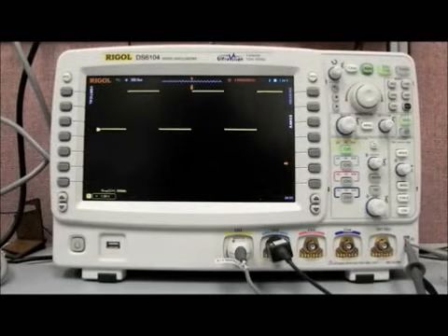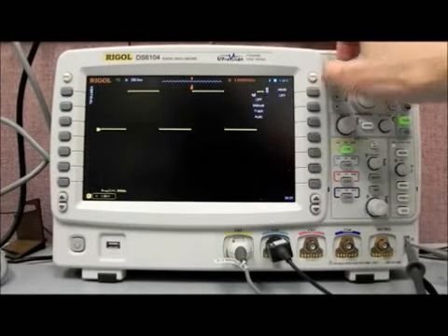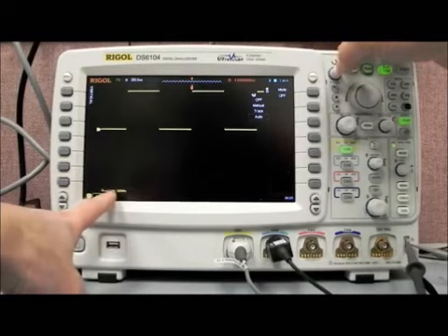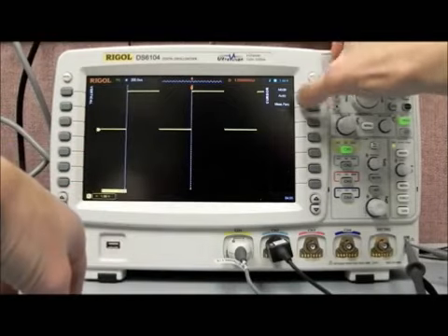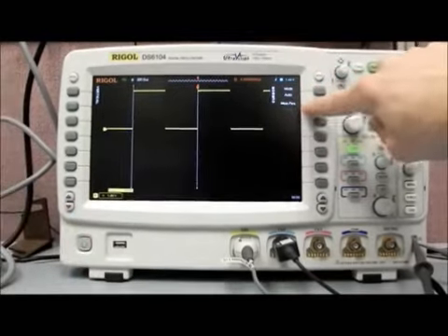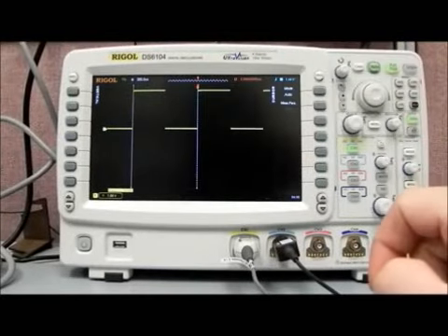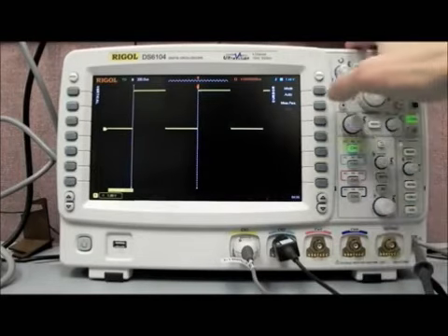And we can also do some other things with measurements and cursors. If we come over here to the cursor area in the menu, pull cursors, and we have a few different modes. We have manual, tracking, and auto. If we have a measurement pulled up over here, and we hit auto, it will actually give us the area frequency parameters. See how it says measurement parameters frequency? And now it's indicating where it's making those frequency measurements. And it's been highlighted, which is really nice.